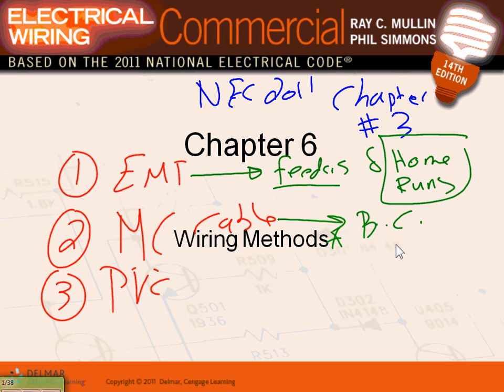For example, I bring an EMT conduit from here to the center of this room into a 4 box, right? 4 by 4 by say 2.5 deep box. From there, I can take an MC cable and feed all these fixtures. Cheap, easy to install. That's the application. I can, from the same box, take another one and feed all these fixtures. Obviously, you might have to have multiple boxes to feed them. That would be where an MC cable would be a really good application, going from the main box in the ceiling to feed other fixtures.